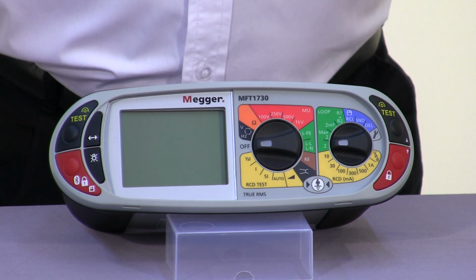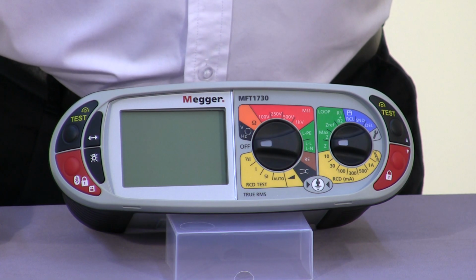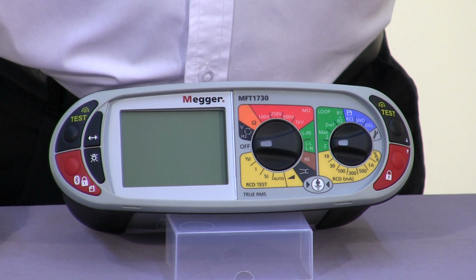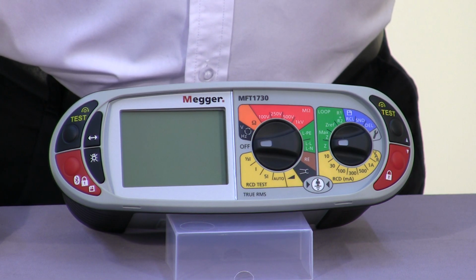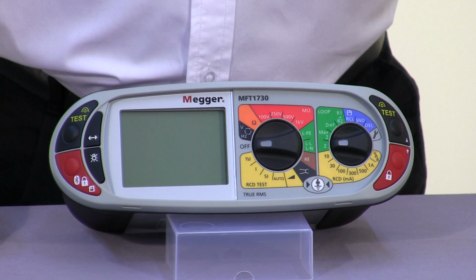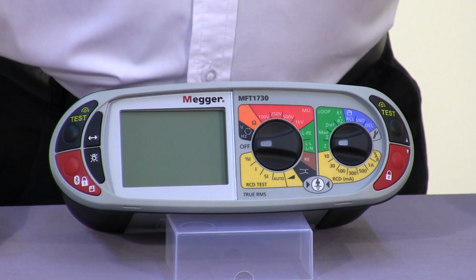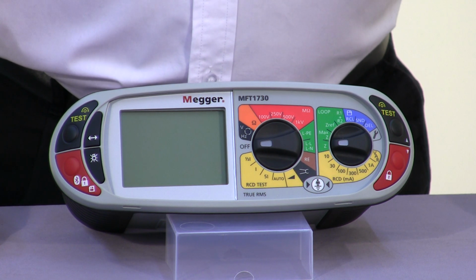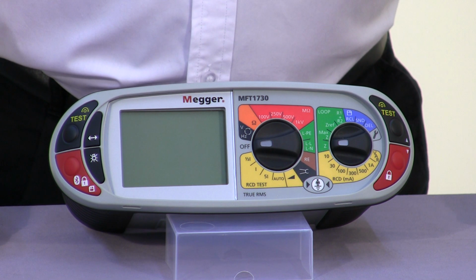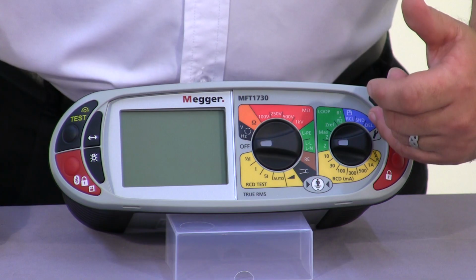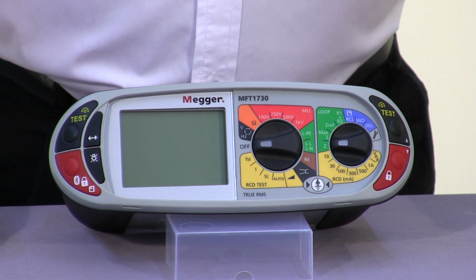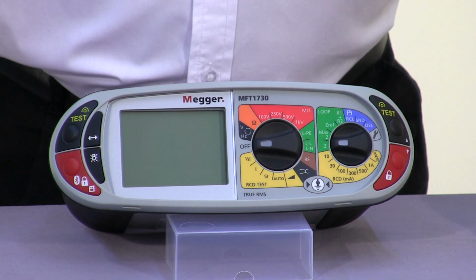Finally, looking at the MFT1730. This unit is rechargeable. The voltage and current measurement are now true RMS, and you'll see that 100 volts has been added to the insulation test range. On the RCD tester, we now have the facility to test the B-type breakers, and we also incorporate a three-wire ground stake or ground resistance tester. The 1730 has the facility to store up to 1,000 results internally, and up here you can see we have the facility to download and recall results directly back to the screen.